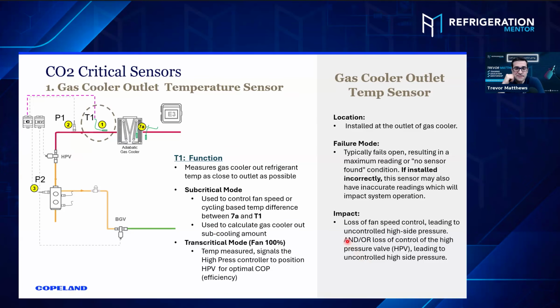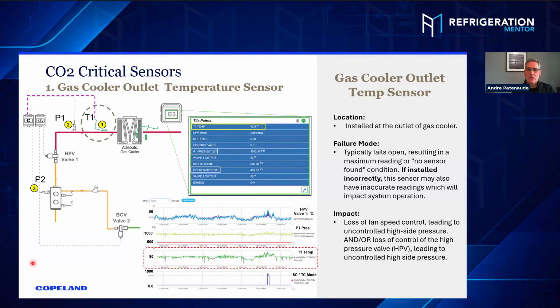Yeah, for sure. So what's the impact of losing that sensor? Loss of fan speed control, leading to uncontrolled high side pressures and/or loss of control of the high pressure valve. If that high pressure valve doesn't get a signal to tell it what to do, it's uncontrolled and then your system crashes. So there are things you can do about that. And you can actually view through the E3 exactly what that T1 temperature sensor is reading.